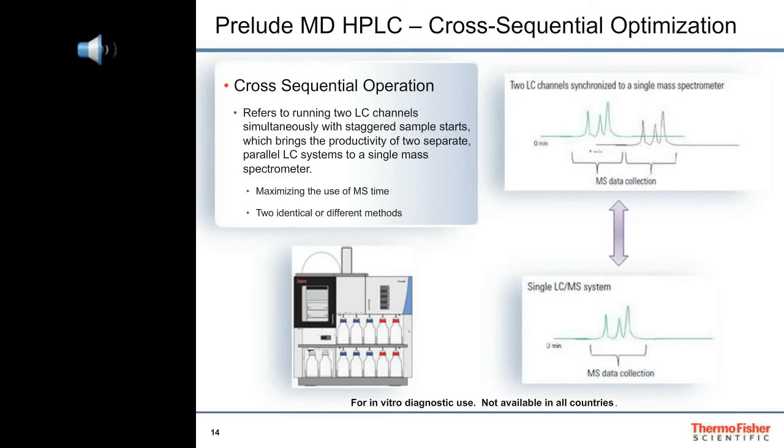Whenever we add sample cleanup to an LC separation method, the total run time increases, but not the data window. The mass spectrometer sits there waiting for the next data window. If the data window is half of the total run time, then staggering injections into two channels will double the sample throughput and maximize the use of the mass spectrometer. This multi-channeling strategy works with any method that elutes the analytes of interest within a fraction of the total run time, including LC methods that don't utilize turbo flow sample cleanup. Cross-sequential operation maximizes the use of the mass spectrometer's time, which a conventional HPLC cannot do.